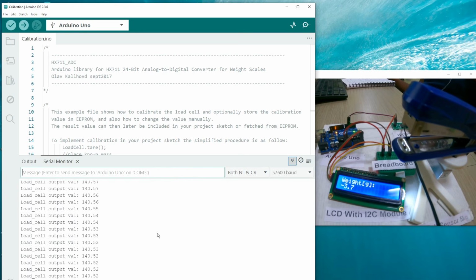Fine. One thing to note about load cells is, typically load cells give you about 0.01% accuracy. For a 5000 gram load cell, and the load cell that we are working with has a rating of 5000 grams, 0.01% of 5000 grams is 0.5 grams. So 0.5 grams error is acceptable for this load cell. Currently we are getting about 0.2 grams of error.